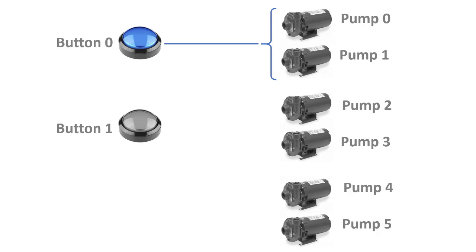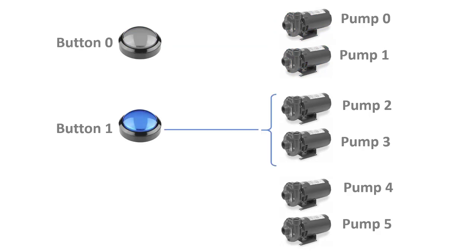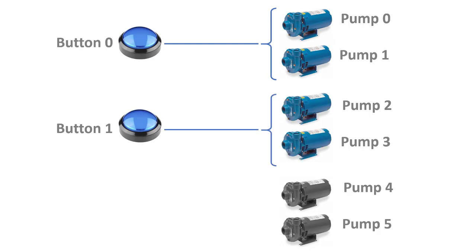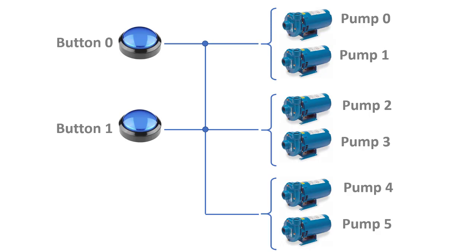The logic of your program should allow an operator to push button 0, which should then turn on pumps 0 and pump number 1. And when you release the button, those pumps should be turned off. When you push button 1, it should result in pumps 2 and 3 being energized. And if you happen to push button 0, turning on pumps 0 and 1, and button 1, turning on pumps 2 and 3, and if you hold both those buttons down together, it should have the added effect of turning on pumps 4 and 5. So let's go to Connected Components Workbench and write a ladder logic program that will have this functionality.